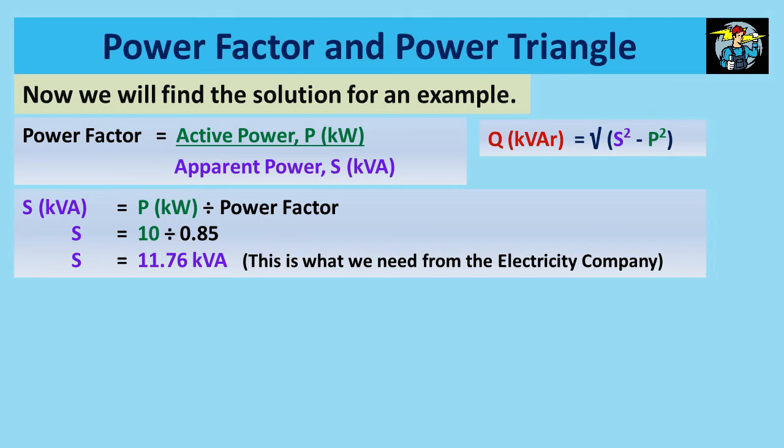P is the value given on the motor nameplate with kW, and the power factor too is given on the nameplate. When 10 is divided by 0.85, we get 11.76 kVA for apparent power S. This 11.76 kVA is what we require from the electricity company to operate this 10 kW motor.